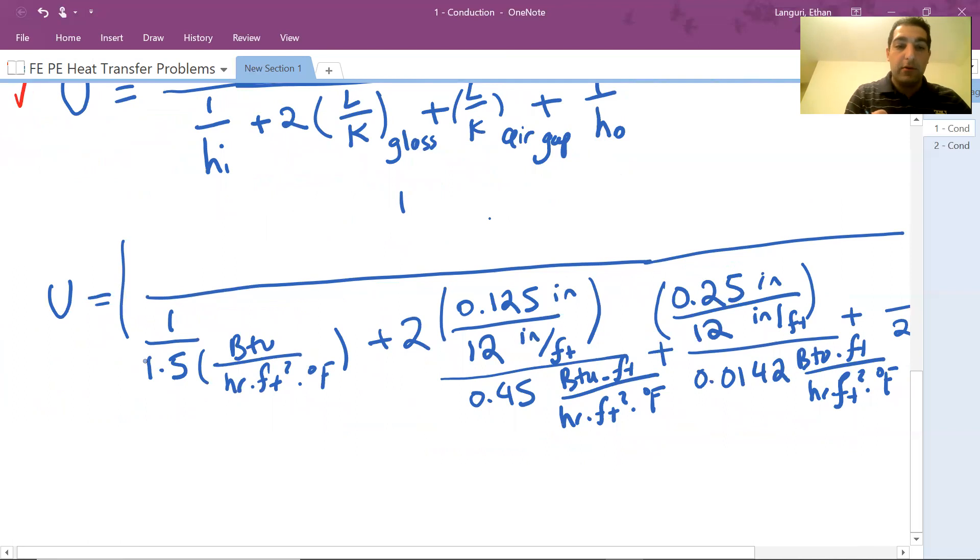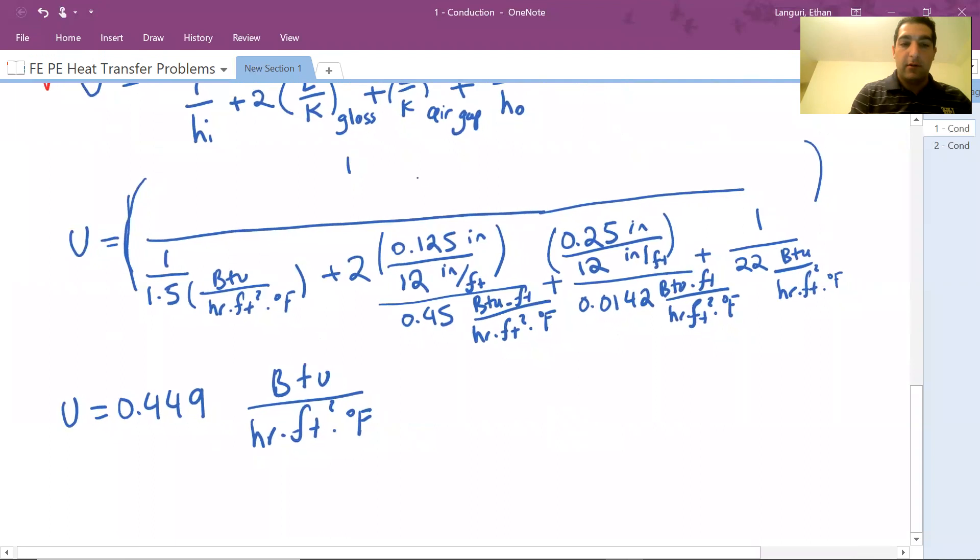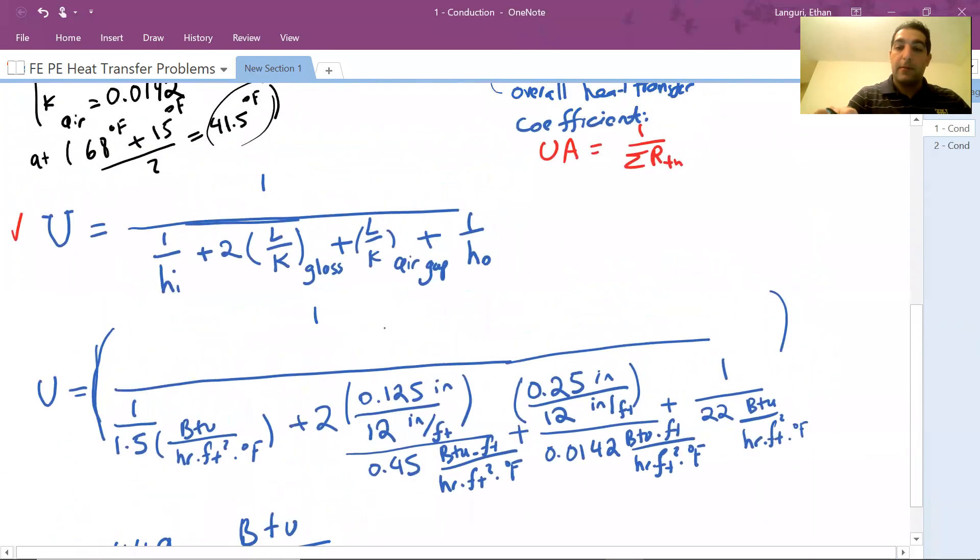Now we need to use your calculator and find the total value for U. If you do this, your U will be 0.449, and the unit for U must be BTU per hour foot squared degree Fahrenheit. Let me make it smaller so everyone can see the whole thing. So this is my overall heat transfer coefficient.